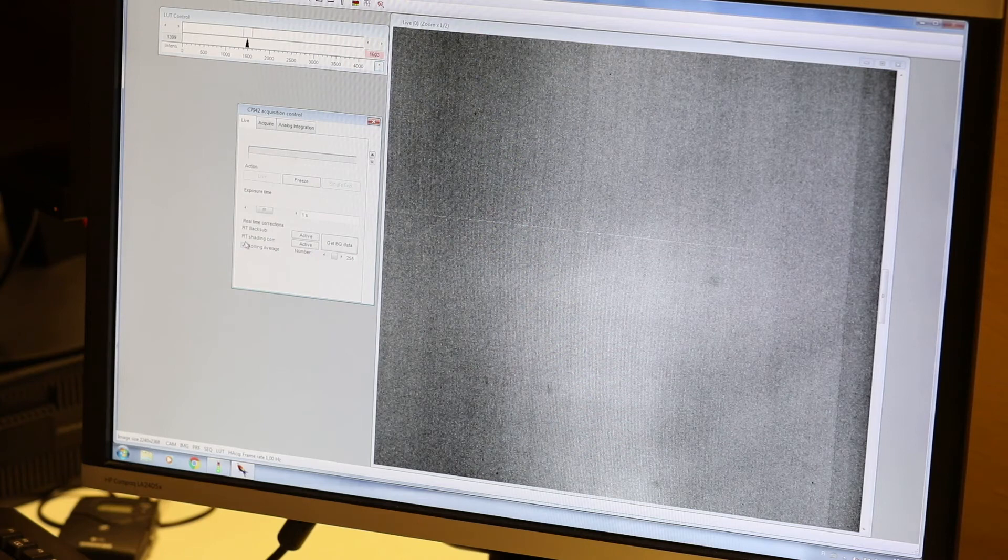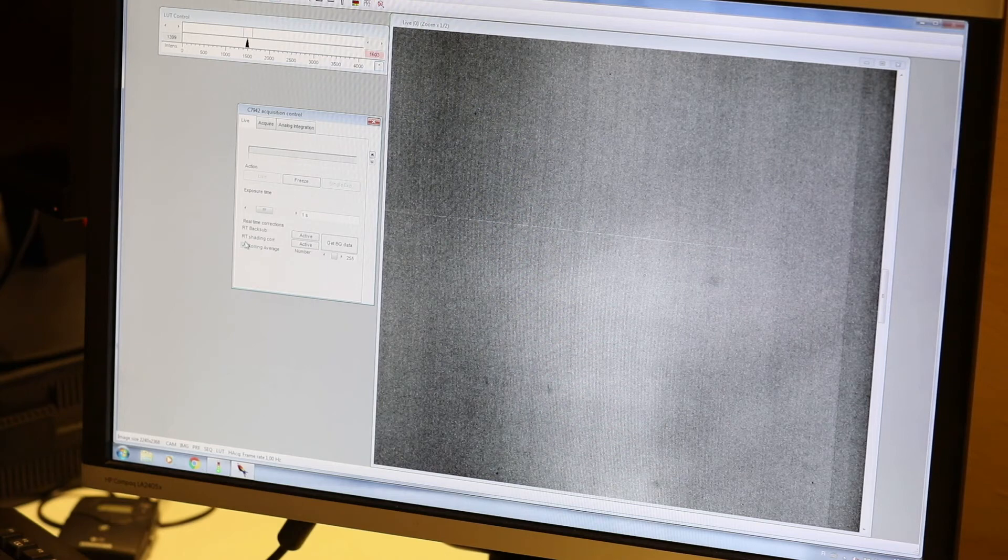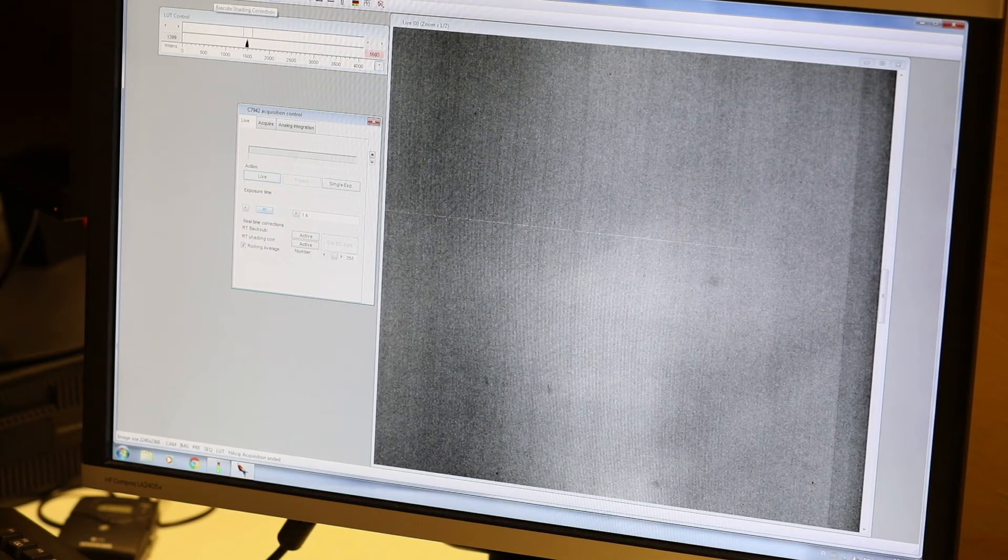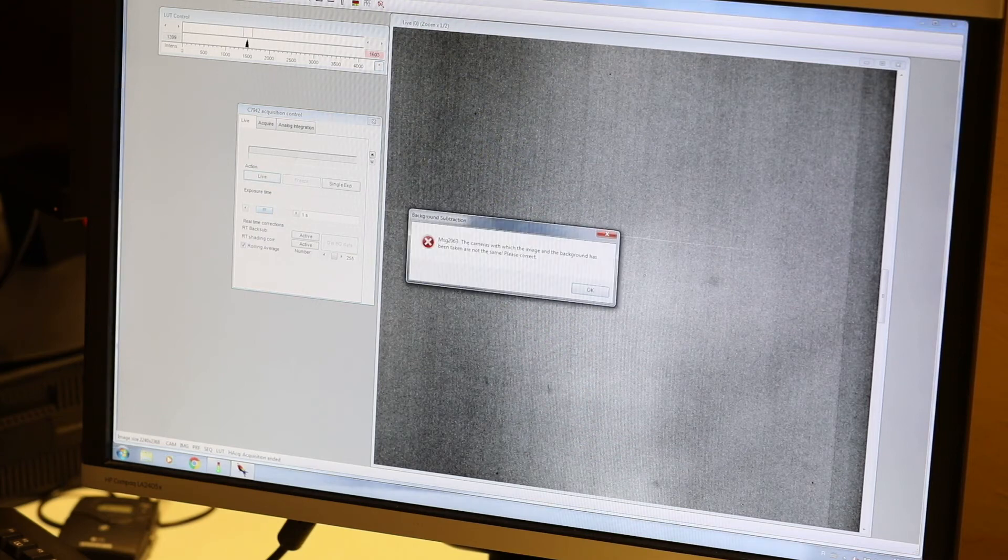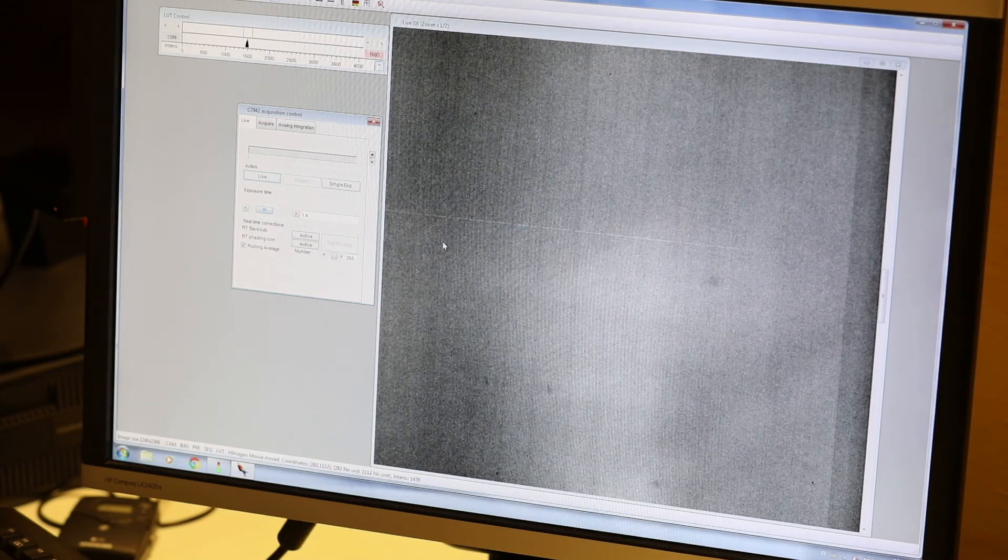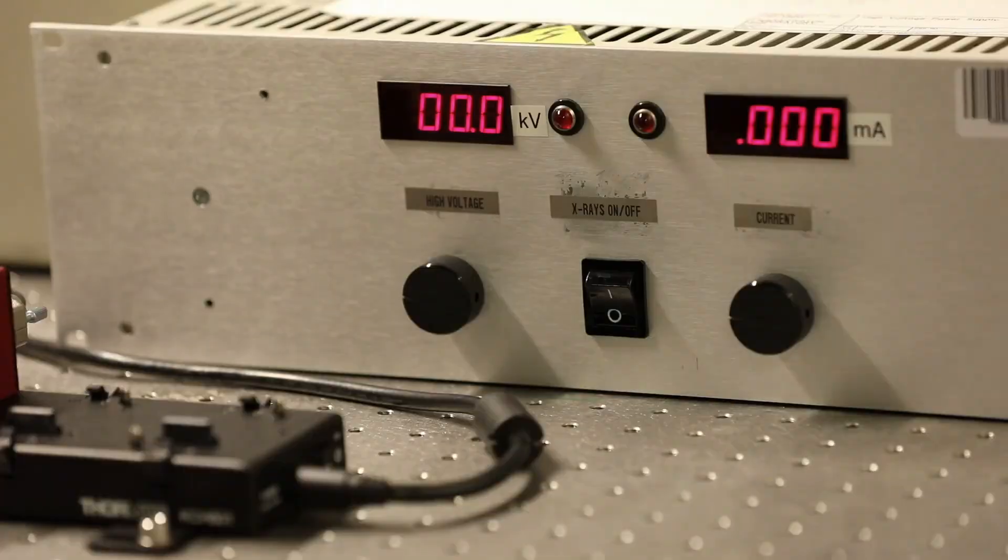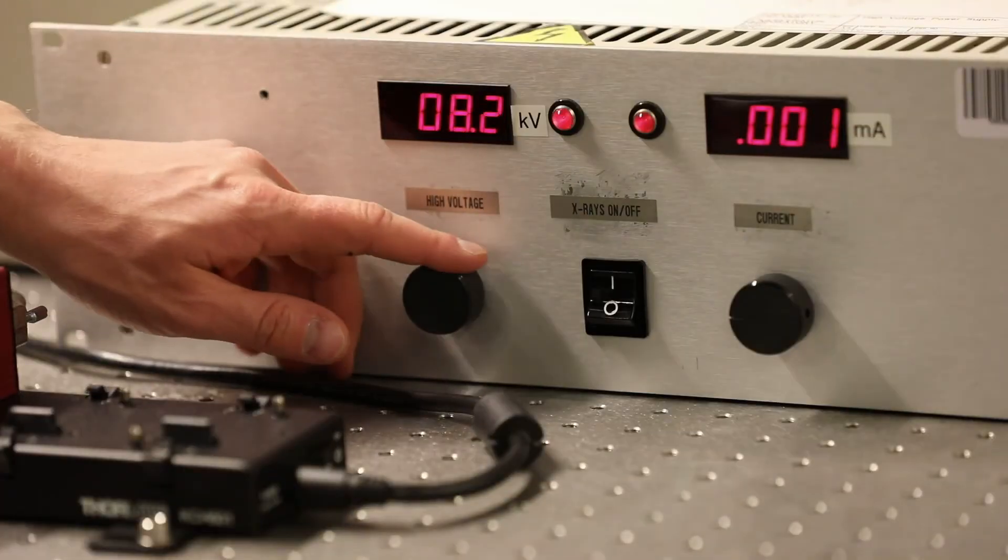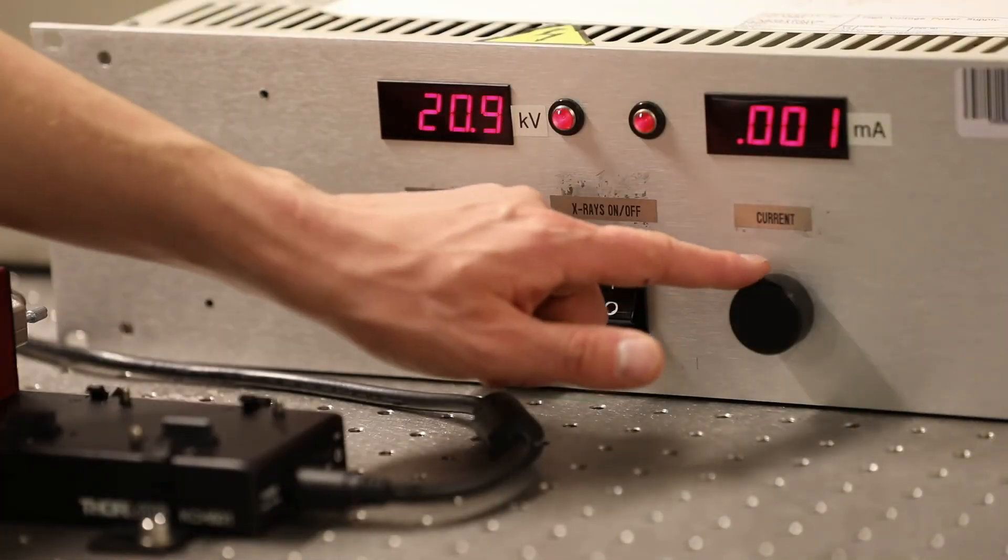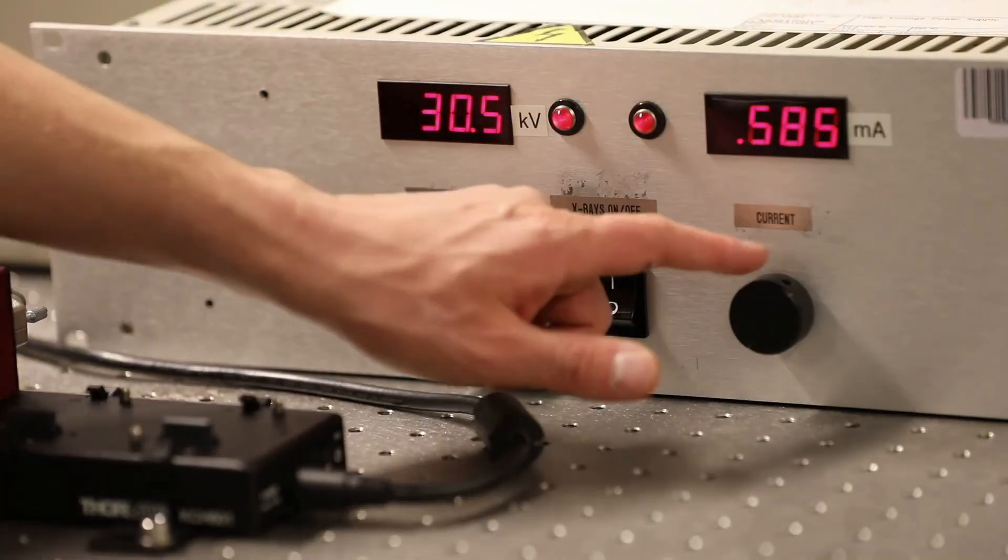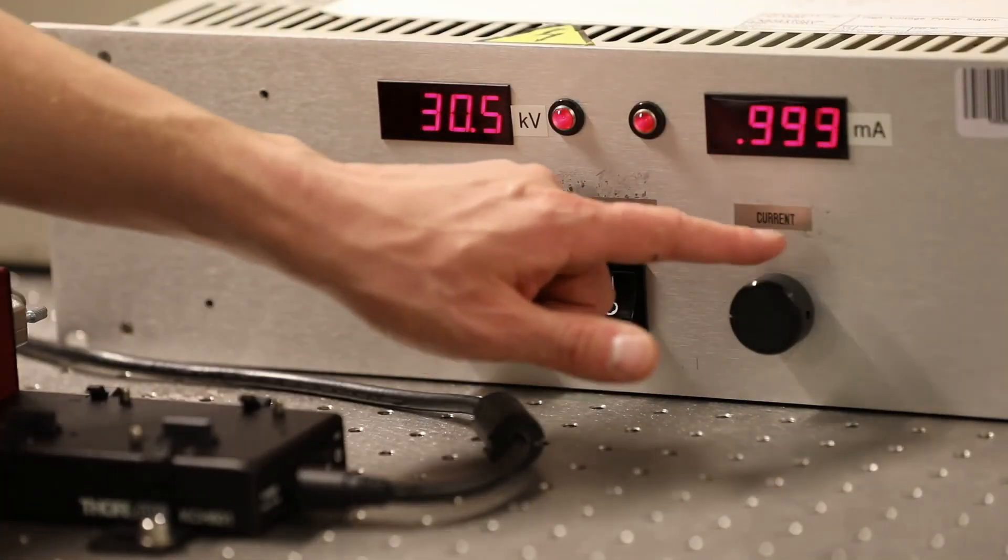Again, we take the calibration image by averaging multiple exposures of the radiation field and subtracting the background from this, resulting in a flat field correction image. Once again, it's important to take the calibration images using the same settings as we will be using in the actual x-ray measurements themselves. The settings to adjust are the detector exposure time, the x-ray tube current, and the acceleration voltage.